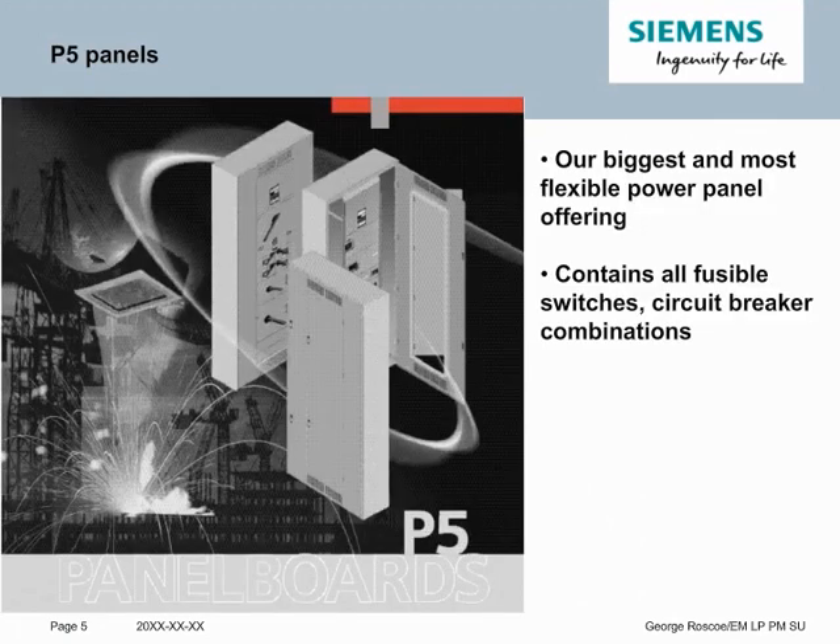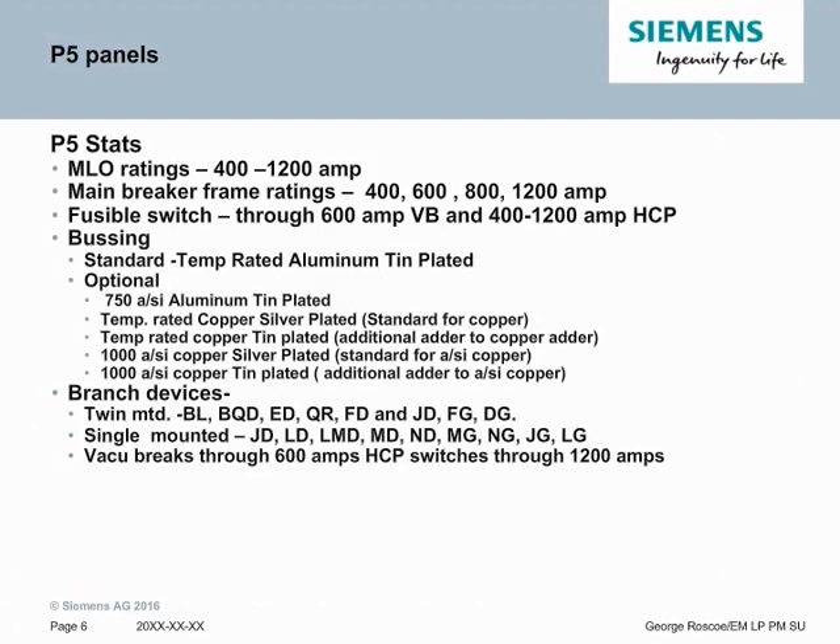The P5 panel is the biggest and most flexible power panel offering from Siemens. It contains all our fusible switch options and all our circuit breaker combinations up to 1200 amps. Main lug ratings are the same as P4's — 400 amps to 1200 amps. P5 adds additional main breakers of 1200 amps and also allows for Sentron 800 amps to fit in a P5. The other key difference is the fusible switches are now up to 600 amp vacu-break and up to 1200 amp high contact pressure switches, making our fuse offerings fully available as mains and branches.